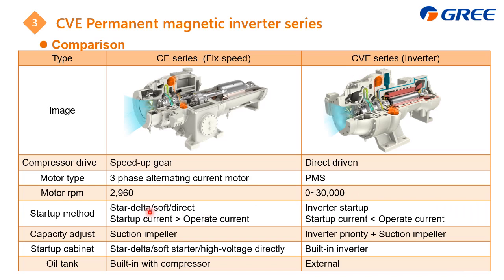For the startup methods, as it is on-off, you can use the star-delta, the soft, or direct startup, which means the startup current is higher than the operating current. For the CVE, as we can change the compressor RPM, at the beginning we can make it the lowest startup current, which means the startup current can be less than the operating current. Very good for the power supply. And for the capacity adjustment method, we have the suction impeller, which adjusts the suction amount. For the CVE, besides this one, we can also adjust the compressor RPM.